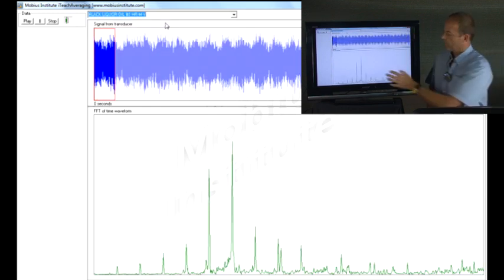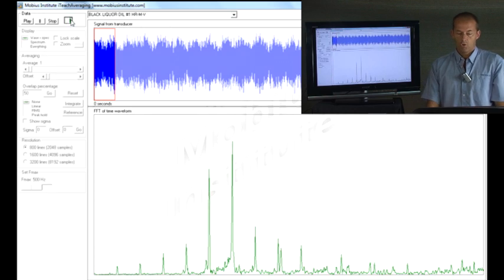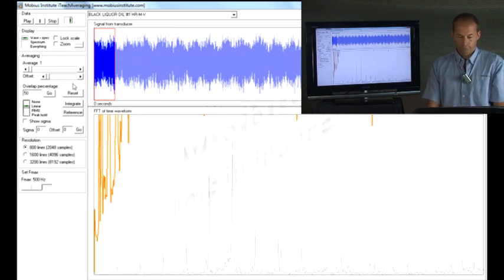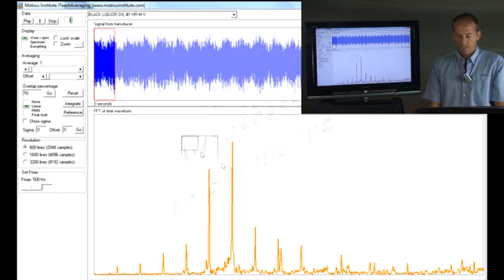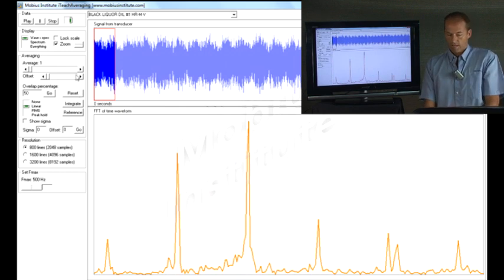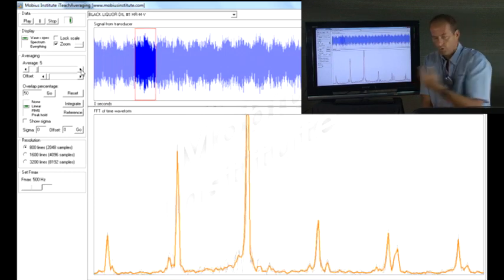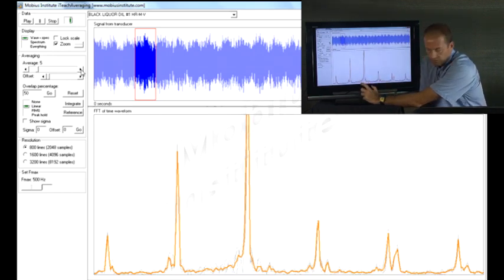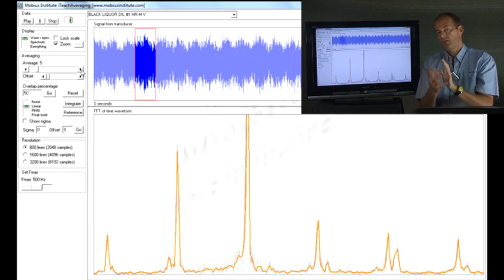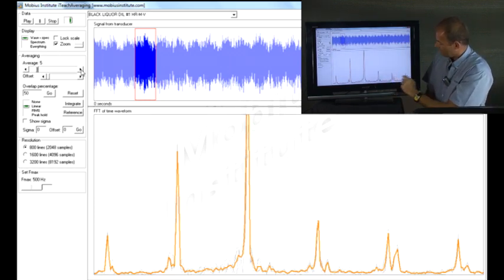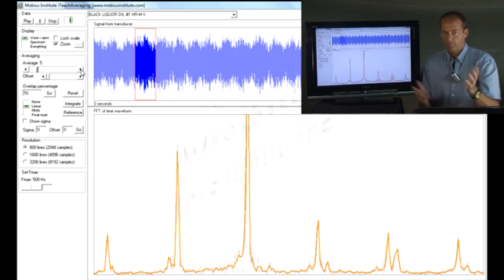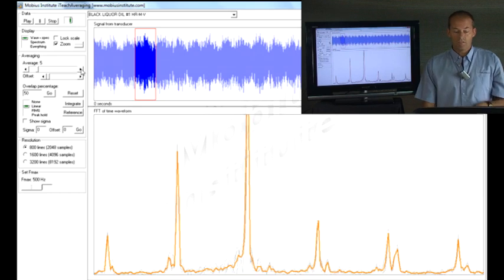Even with this little sample here if I turn on my averaging option, let's reset that and we just take a little look, this is just a pretty simple piece of vibration. But if I go through and show the averages if you look on the screen here it's a bit easier than watching on this screen but you see the light gray areas are the individual spectra that have been averaged together to create the orange one and you can see that in a lot of places the vibration didn't vary very much, the average is good, four averages would just be fine in those cases.